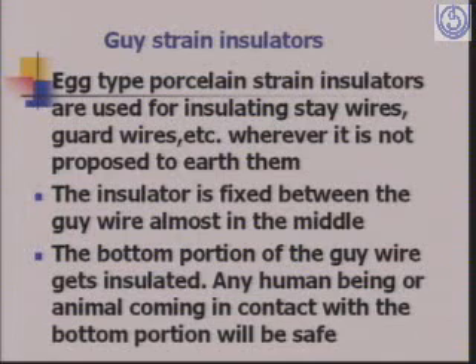Then we have the guy strain insulators. Egg-type porcelain strain insulators are used for insulating stay wires, guard wires, wherever it is not proposed to earth them. The insulator is fixed between the guy wire almost in the middle. The bottom portion of the guy wire gets insulated, and any human being or animal coming in contact with the bottom portion will be safe. Basically, the idea of the guy strain insulator is to keep the bottom portion insulated from the pole, so that any human being or animal coming in contact with the bottom portion of the stay wire will be safe.